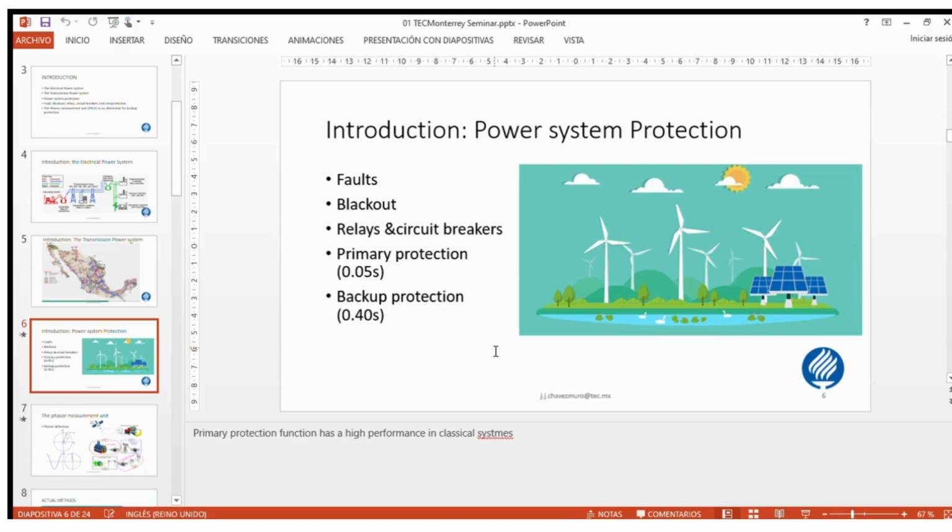So the current is not gonna be 7 or 20 times more, it's gonna be at most two times more. This makes it really challenging for the relay. Actually, some of them become blind, so they might not operate during a fault.